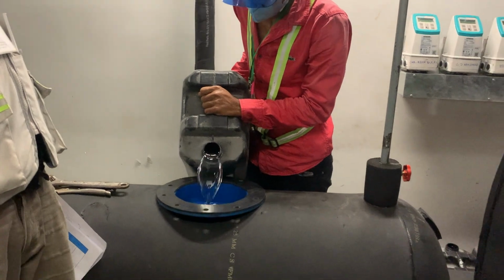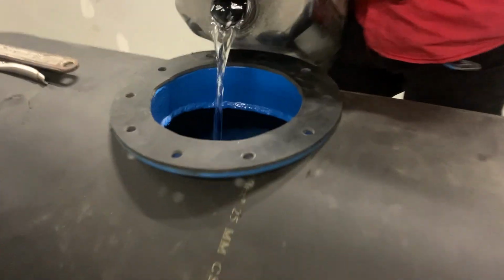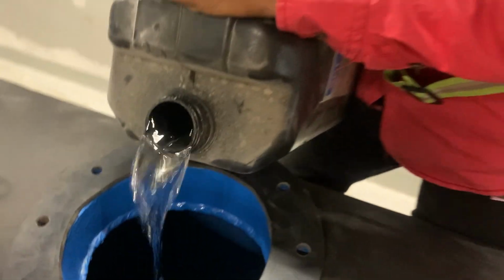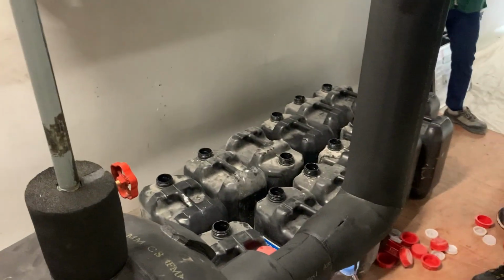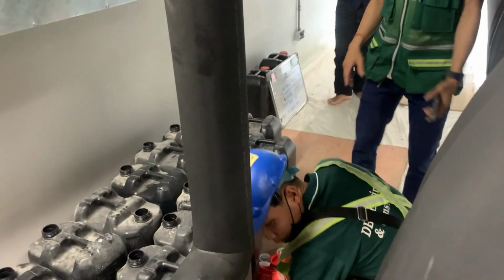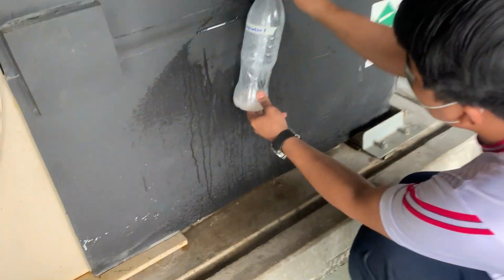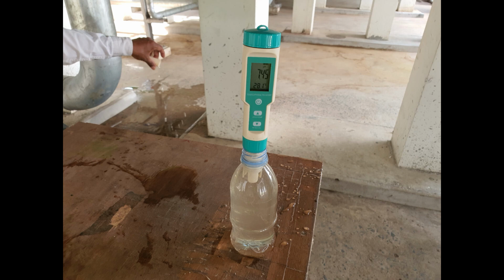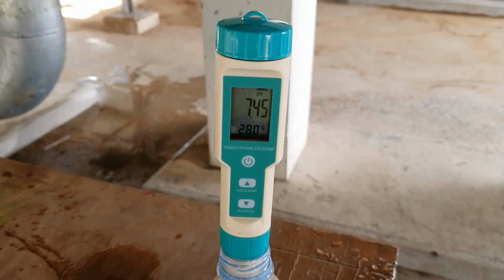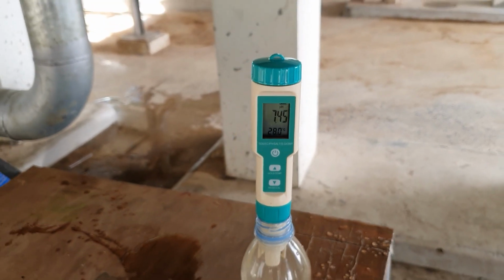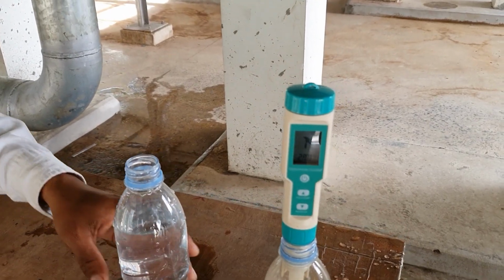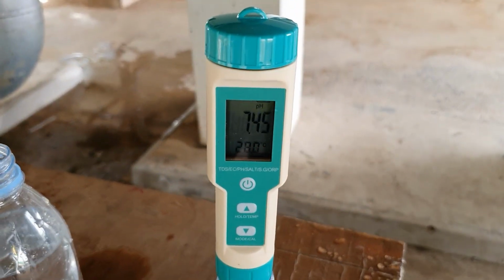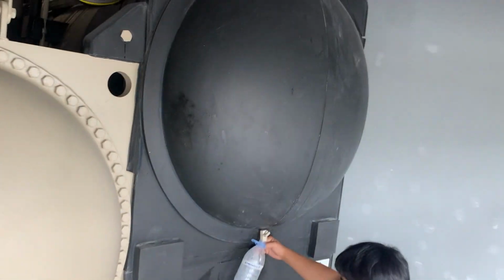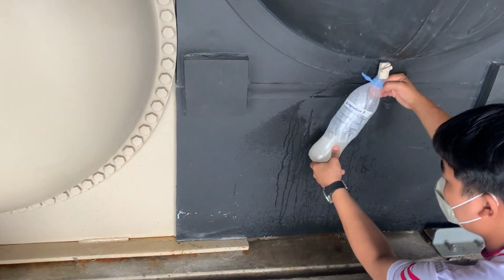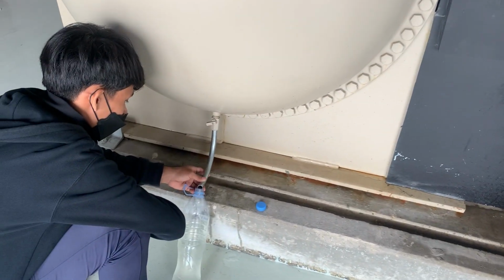We can see the result of the water after we do the flushing, and then we check the water quality and test it with the lab. This is very important for the chiller system, because our chillers work with the water system, so the water must be acceptable according to the lab testing.